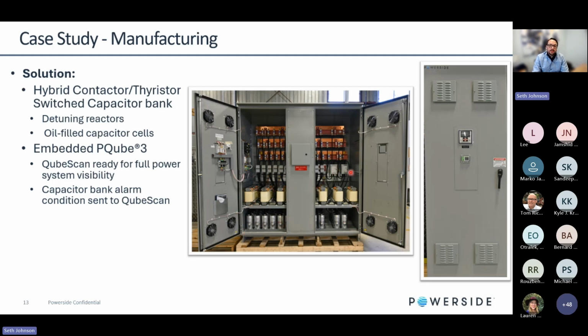When you're using a thyristor or a zero voltage crossing switch, you could turn them on and off instantaneously, because when they turn off, you don't have residual voltage in the capacitor cell, so you do not have to wait for it to discharge. And so when we looked through some of the existing equipment on site at the facility, we saw a lot of contactors that were burnt up, a lot of blown fuses, and we went into some of the control parameters, and everything was set to respond relatively quickly, but it led to premature failure of the equipment.